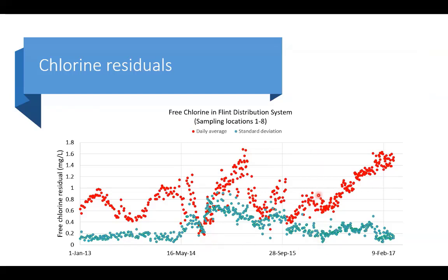It was in October of 2015 that they switched back to purchasing water, and this was done in conjunction with, or under the guidance of, EGLE, then MDEQ, to try and flush out the system and ensure that all areas of the distribution system had sufficient chlorine residual.